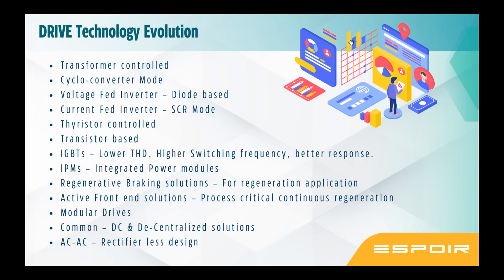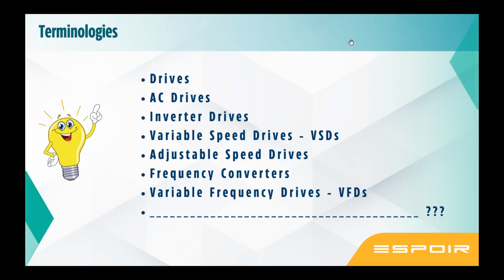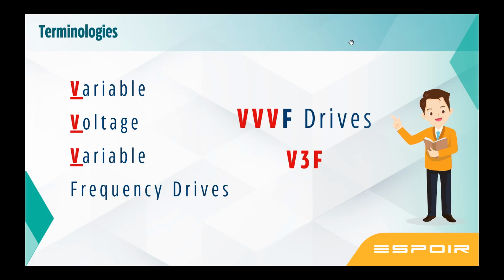So what are the terminologies? You hear drives, AC drives, inverter drives, variable speed drives, adjustable speed drives, frequency converters, variable frequency drives. These are all common terminologies which you hear from different industries. Some industries call it frequency converters, some call it inverters, and some as simply drives. But the right terminology is variable voltage, variable frequency drive, because we are not just changing the frequency, we are also changing the voltage. So it is called a variable voltage, variable frequency drive.